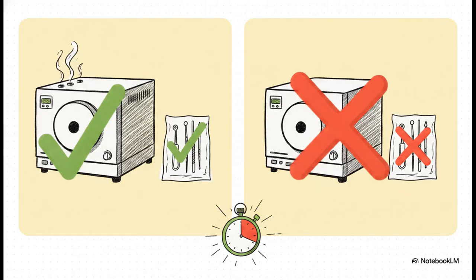And listen, not all autoclaves are created equal either. You have the Class B vacuum autoclave, which is the recommended standard for wrapped and hollow instruments. Then you have the Class N gravity displacement unit. Class N units actually cannot sterilize wrapped packs or lumened instruments. They are, frankly, completely unsafe for piercing equipment. Plus, undersized units, even if they are Class B, create this immense pressure on staff to rush the cycles. And a rush cycle is an incomplete cycle, for sure.